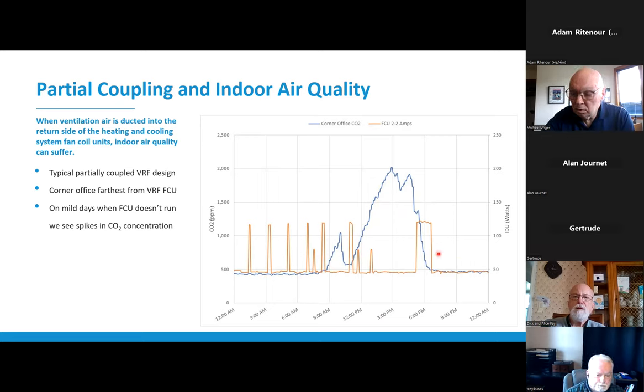We actually have other data for this particular office. And so this wasn't the worst day. We actually saw on some days when the fan coil unit almost didn't run at all, the CO2 concentration reached above 3000 ppm in that corner office. So it's pretty clear that in this type of design, partial coupling, ventilation isn't effectively being delivered to all of the spaces.